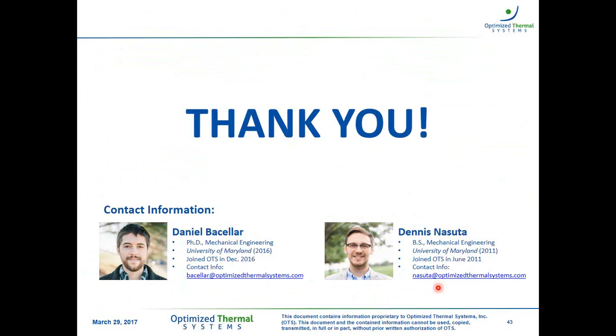So as far as what we have tested, we've developed a couple of systems in-house that have 5 millimeter heat exchangers, and in all of those cases, we haven't seen a major consequence in terms of COP reduction or capacity reduction due to the refrigerant pressure drop. That's mostly because we design these systems to have the number of circuits that's required to ensure that we don't have excessive pressure drop. Hopefully that's helpful.